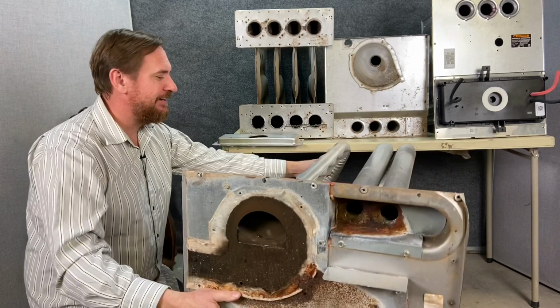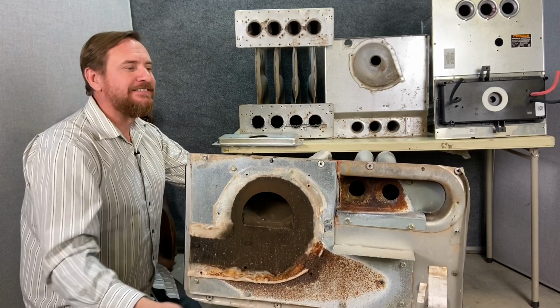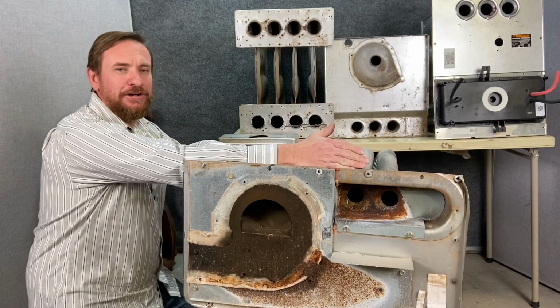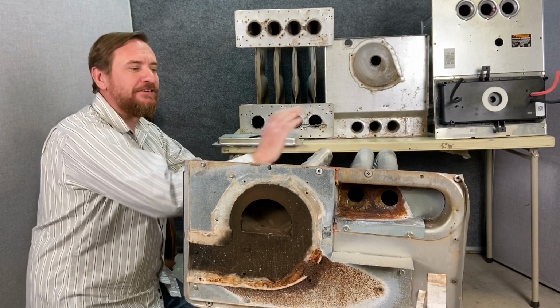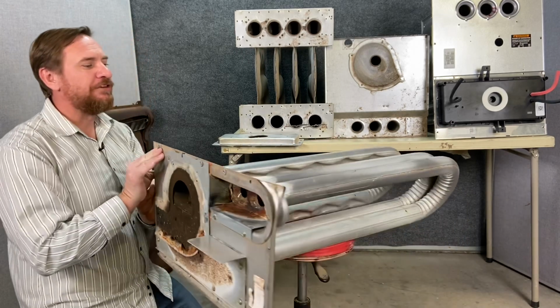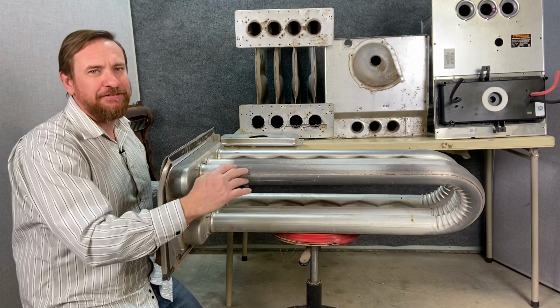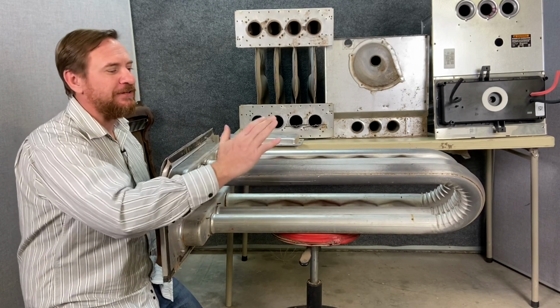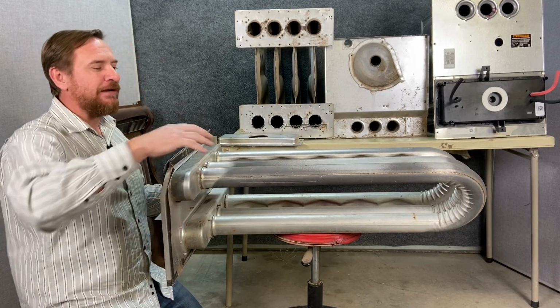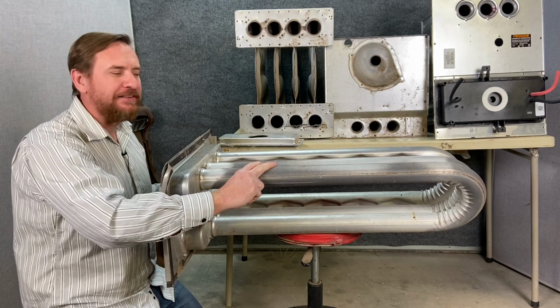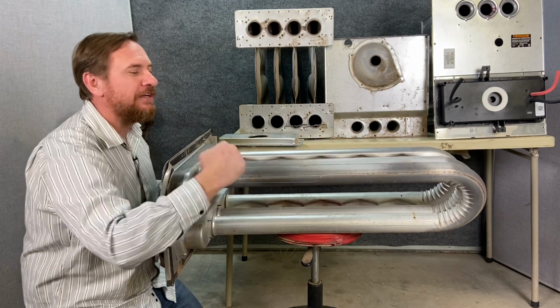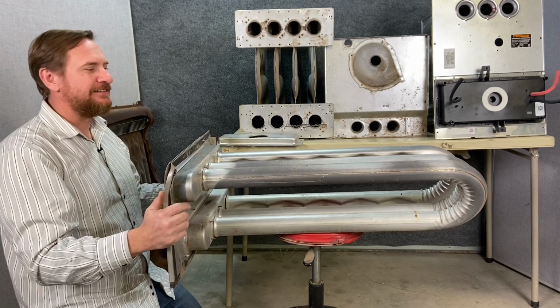Something like this could be very dangerous, but its job, again, is to separate the flames and combustion gases from the air of the building, while also exchanging the heat from the flames and the gases to the air in the building. So it keeps them completely separate. Many residential units also use tubes like this, even though they weren't quite so long, they still use tubes in the same exact style.